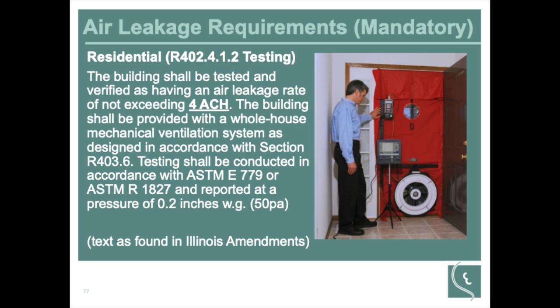We did that at one place—they put the fire out and closed the doors, but there was still enough leakage that we couldn't complete the test. I recall vinyl flooring, loose lay, getting lifted right off the floor into a big bubble from the air leakage. You'll find leaks in the most odd places in a building—it's a very interesting test, and not that difficult to do.